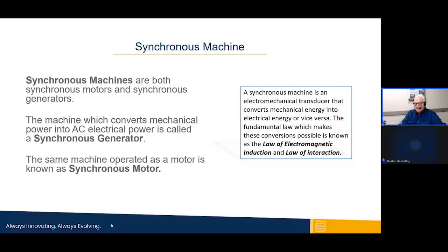What makes the machine a synchronous machine is that the rotor imparts a spinning electromagnet that links the rotor through the rotating magnetic field to the alternating current in the stator. The electromagnet is energized by the current coursing through the magnetic windings of the rotor. The current is supplied by the exciter. The amount of current provided from the exciter is a variable that has critical importance to the operation of the synchronous electrical machine. Next slide, please.